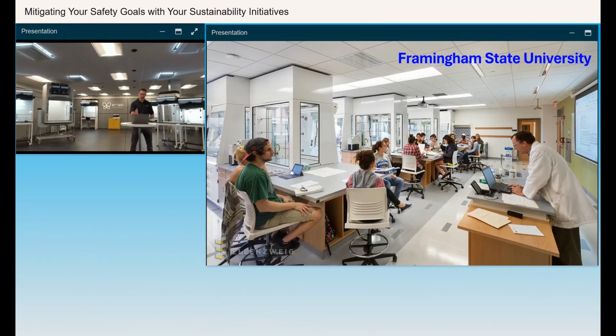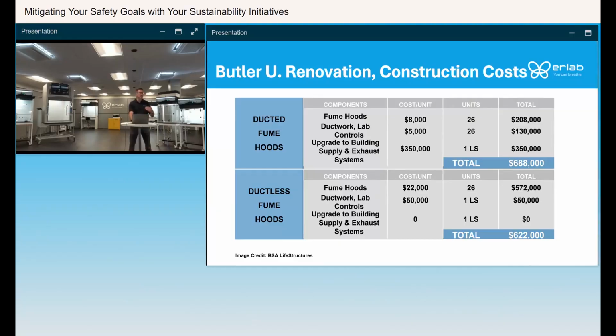Now, this is a picture of one of the 8 hood teaching labs there. So if you are installing fume hoods, say on an island or depending on where they are in the lab, take into consideration the views. You may want to put a clear glass panel on the back, side panels with glass, just so it increases visibility. Framingham State, we're actually there this summer doing their second filter change that was installed in 2016. And they're saving about $24,000 a year in operating expense in just the makeup air in these, especially these high-density fume hood labs. Now, the next example is Butler University.